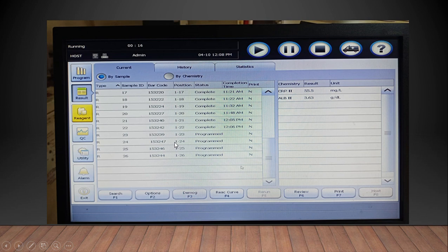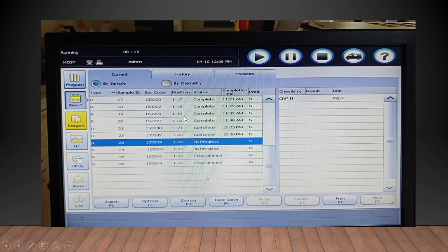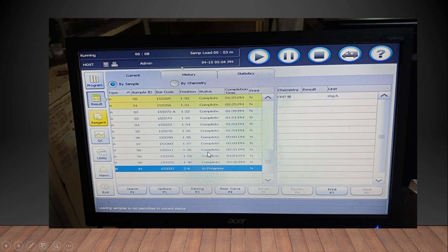The moment you go to the result window, you can see that 23 to 26 is showing as programmed. Immediately the running will start, it may take 1 or 2 minutes, and the instrument will begin the countdown as 16 minutes or whatever time the particular test is going to take, depending upon what test we have given. It starts the stopwatch and begins the procedure. For example, after 1 minute it shows this test is in progress, then this number is also in progress. Similarly everything will be in progress.